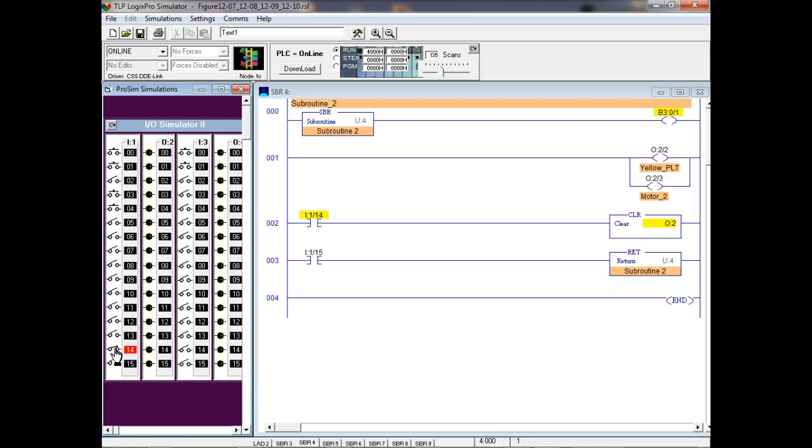Yeah, all these conditions, we can go through that. We can move around. It's really neat, and that's what's so neat with a computer. We can do sequencers, but you'll see a sequencer on a PLC. It's nothing but a bunch of cam gear. It's got cams all over it, and a motor that turns it. Then limit switches hit those cams and make the thing run in a certain sequence. That's the way we would have to do it on motor control, but here we just set up any type of sequence we want, which is pretty neat.